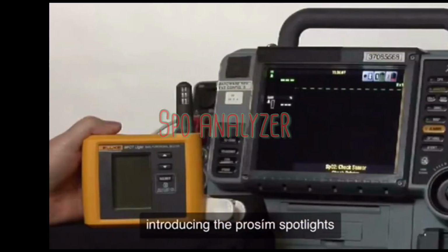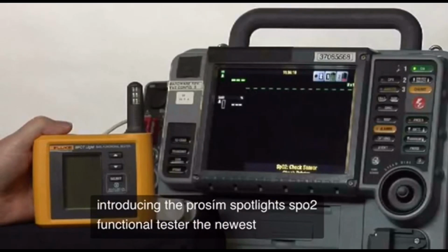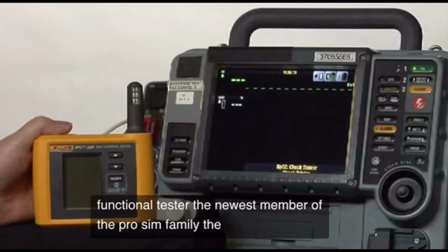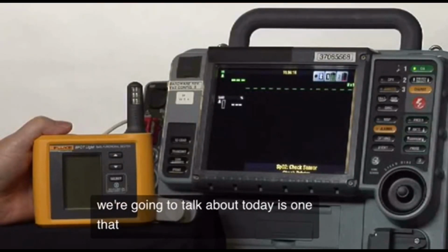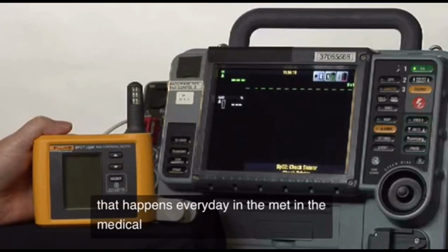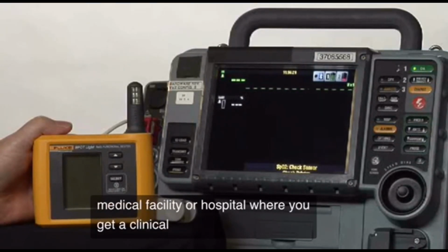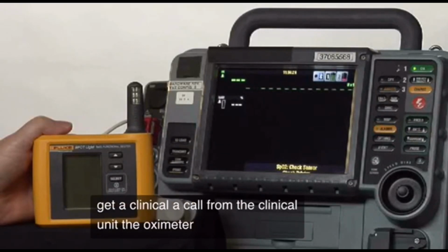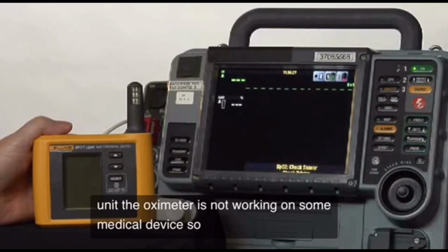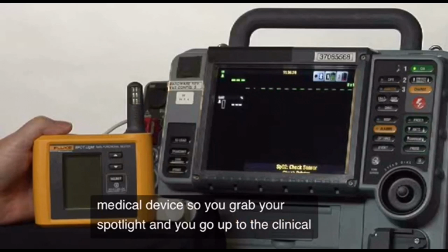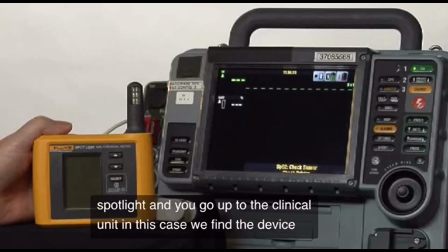The ProSim Spotlight SpO2 Functional Tester, the newest member of the ProSim family. The scenario that we're going to talk about today is one that happens every day in the medical facility or hospital, where you get a call from the clinical unit. The oximeter is not working on some medical device. So you grab your Spotlight and you go up to the clinical unit. In this case, we find the device turned on.